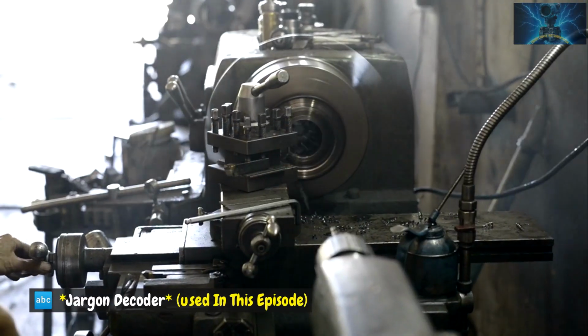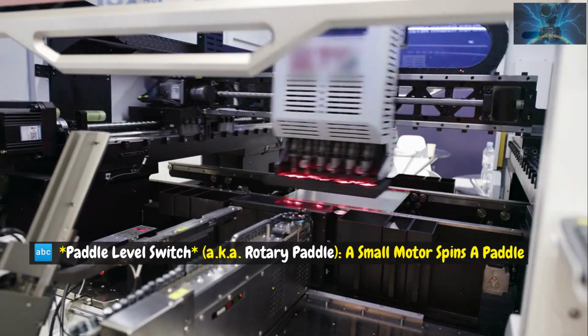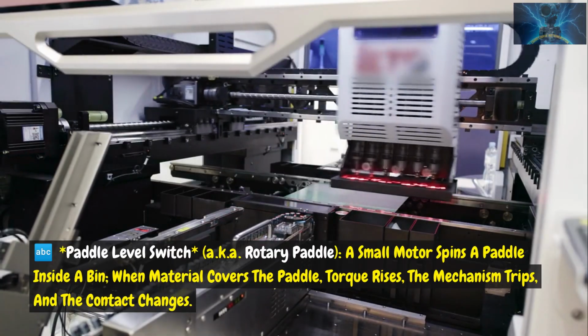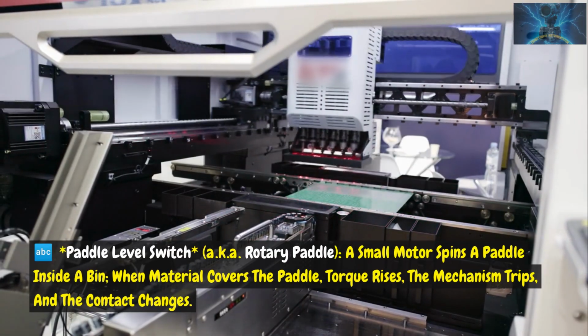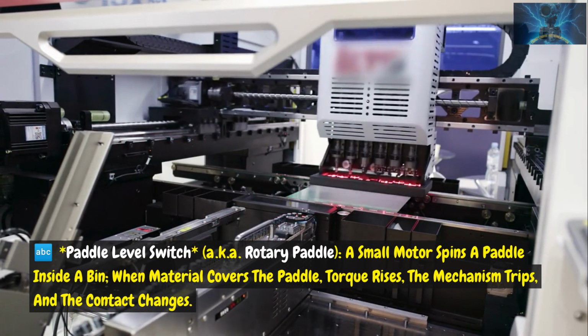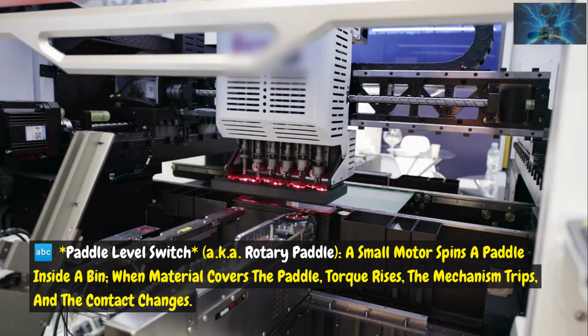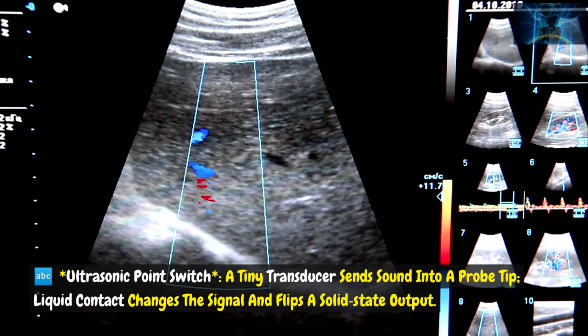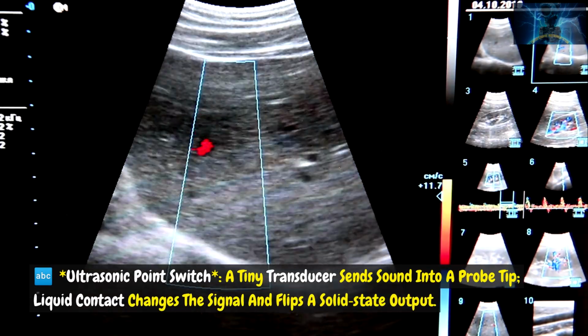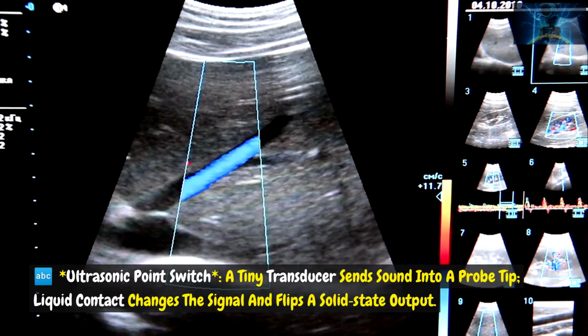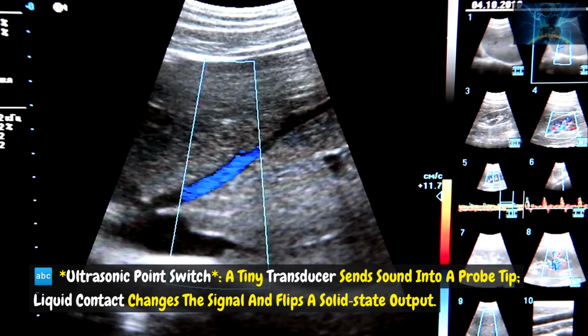Jargon decoder, used in this episode. Paddle level switch, aka rotary paddle: a small motor spins a paddle inside a bin. When material covers the paddle, torque rises, the mechanism trips, and the contact changes. Ultrasonic point switch: a tiny transducer sends sound into a probe tip. Liquid contact changes the signal and flips a solid-state output.